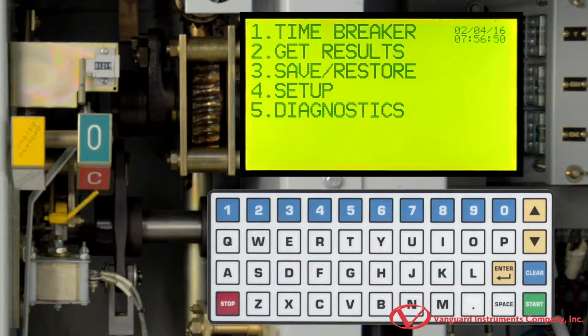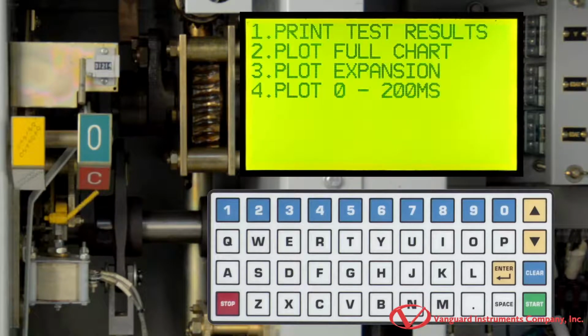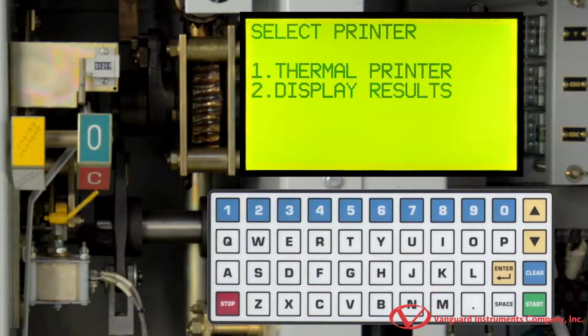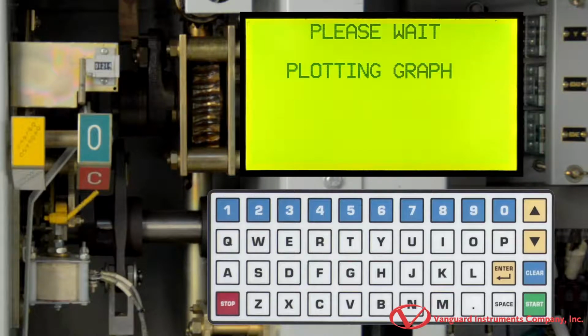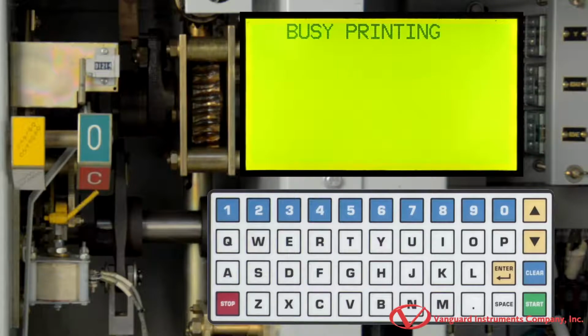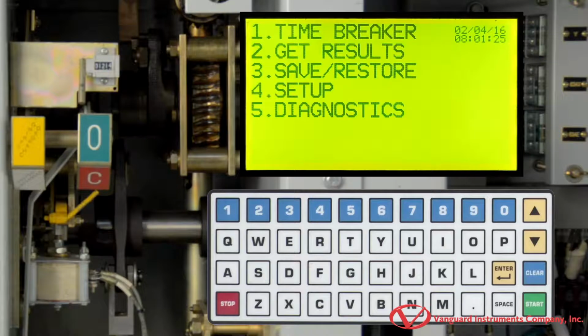Once we've performed the test, we can print the test results to the unit's built-in thermal printer. To print the test results, select Get Results by pressing the 2 key. We are now presented with multiple options for printing the test results. We're going to select Plot Full Chart by pressing the 2 key. Now press the 1 key to select Thermal Printer. And now the test results are going to be printed on the unit's thermal printer. Once printing is completed, you will be returned to the main menu.